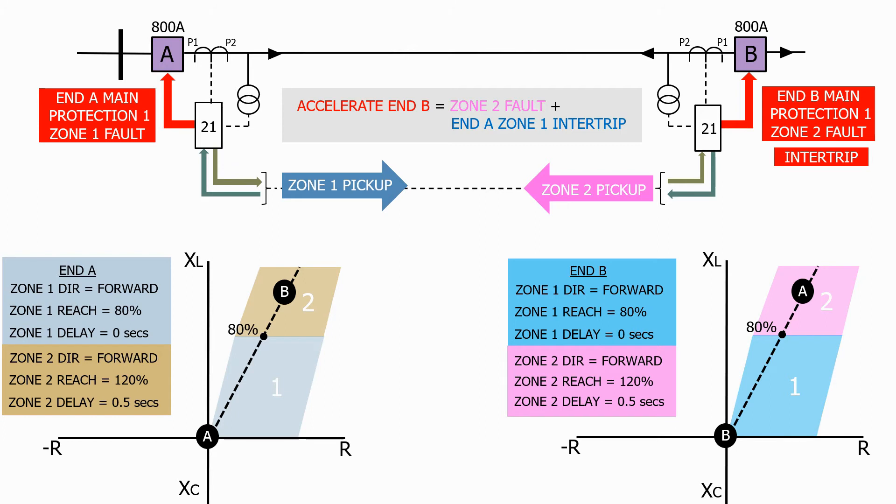So by adding the communication circuit we can now clear instantaneously any fault that appears between the current transformers on the feeder. This type of impedance relay scheme is called an acceleration scheme, as the relays use the communication circuit to accelerate the operation of the relays and remove any time delays.